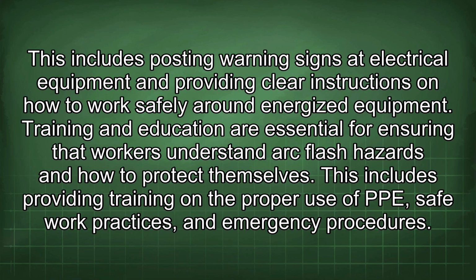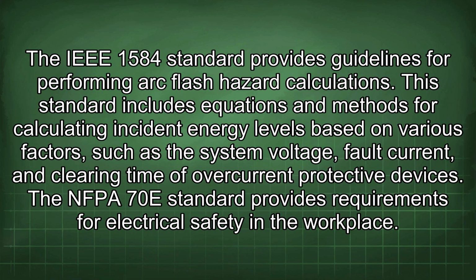Training and education are essential for ensuring that workers understand arc flash hazards and how to protect themselves. This includes providing training on the proper use of PPE, safe work practices, and emergency procedures. The IEEE 1584 standard provides guidelines for performing arc flash hazard calculations. This standard includes equations and methods for calculating incident energy levels based on various factors such as the system voltage, fault current, and clearing time of overcurrent protective devices.